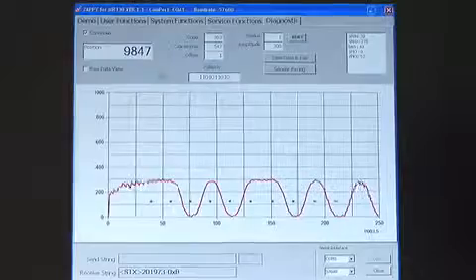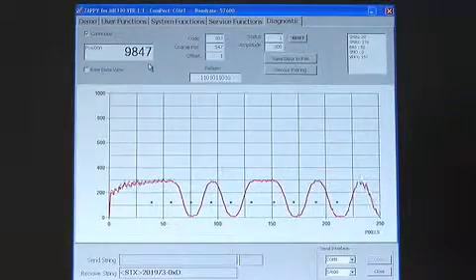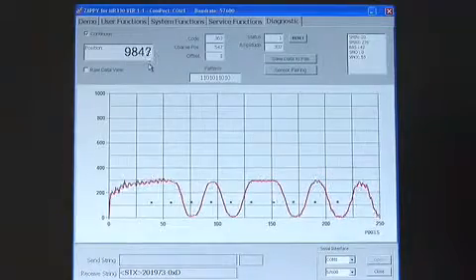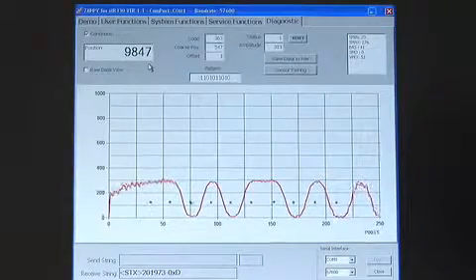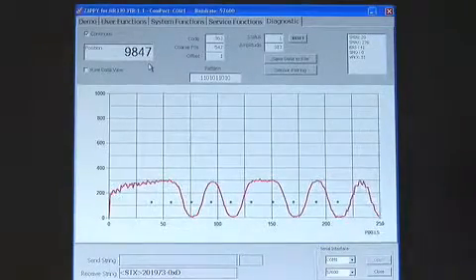Rather than using light intensity, Micronor ingeniously utilizes the light spectrum as an information carrier, making this a very robust position sensor. Again, note that the position readout does not change when the light amplitude is brought back to the previous level.